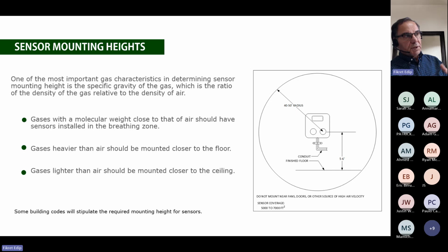For each sensor, what is the radius, the coverage? The typical sensor in a perfect environment has a 40 to 50 feet radius coverage, as you can see here, which equates to 7,000 square feet. But that's not cut and dry. That doesn't apply to everything. In a chiller room application, you don't look at the mechanical room size. You look at the quantity, the number of chillers in the room. In a smaller room, if you have 2 chillers, you put 2 sensors. If your chiller is too large, I don't know exactly the tonnage of that chiller, often you use 2 sensors.